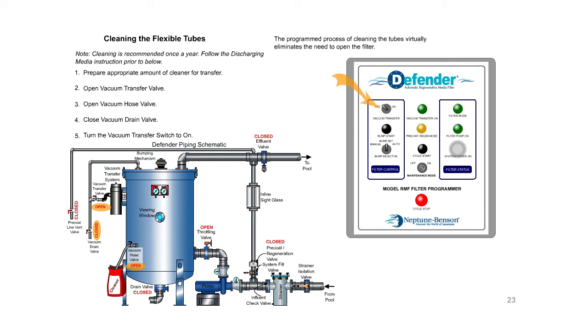Cleaning the flexible tubes. Cleaning is recommended at least once a season. Follow the discharging media instruction prior to these steps. The programmed process of cleaning the tubes virtually eliminates the need to open the filter. Prepare appropriate amount of cleaner for transfer. Open vacuum transfer valve. Open vacuum hose valve. Close vacuum drain valve. Turn the vacuum transfer switch to on.